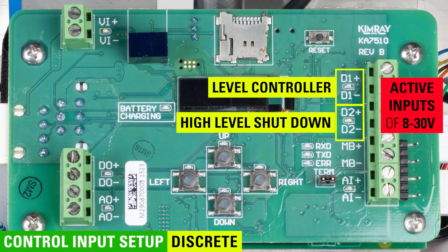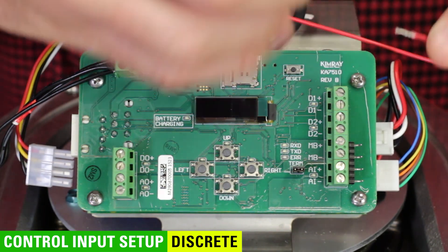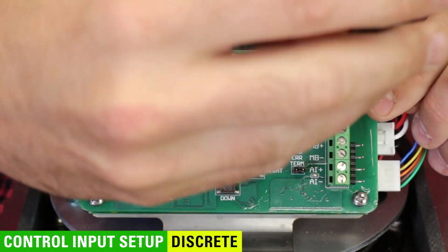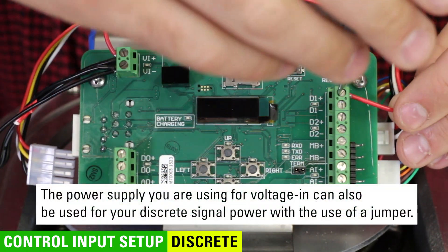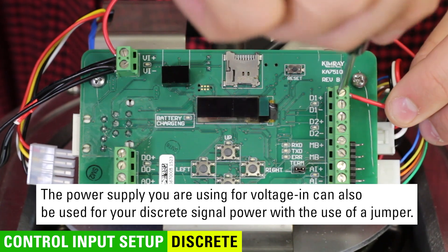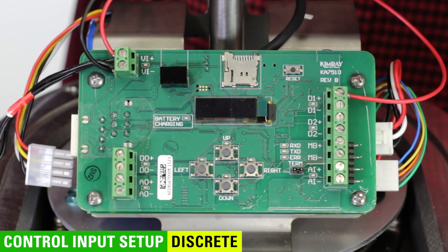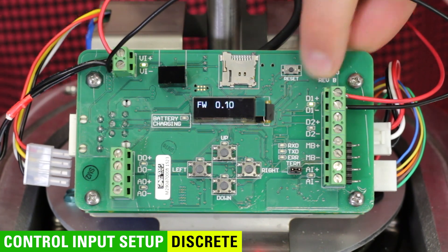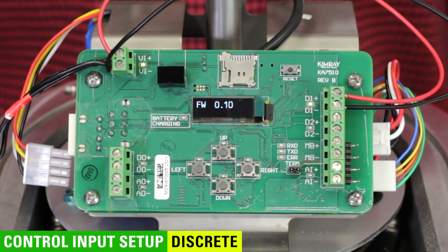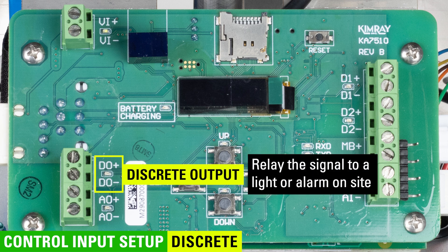You know your connection is complete when the green LED is on. If you don't need that override signal, you can just wire discrete 1 and it will function without a discrete 2 signal. The power supply you are using for voltage in can also be used for your discrete signal power with the use of a jumper. When installing a jumper, make sure power is disconnected from the actuator. Discrete output, labeled DO on the board, can be used to relay the signal to a light or alarm on site.